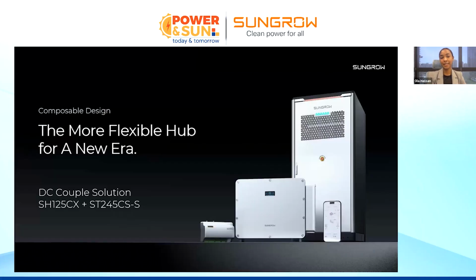Moving into the DC coupled solution, which is our newest innovation. So we have the SH125CX, which is a hybrid inverter with 125 kilowatt output, and it comes with a battery as well. As you can see here, it's similar to the power stack. However, the difference is there's no PCS here because the PCS is built inside the hybrid inverter version itself.